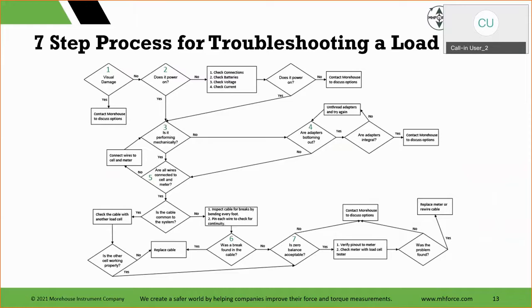Does it power on? Yes, no. Is it performing mechanically? Here's the things. Does it power on? No. Check connections, batteries, voltage, current. I cannot tell you how many times we've set up instruments and forgotten to put the batteries in. It's very frustrating when you do it. As a tech for 15 plus years of my life, you have those moments where you just forget.